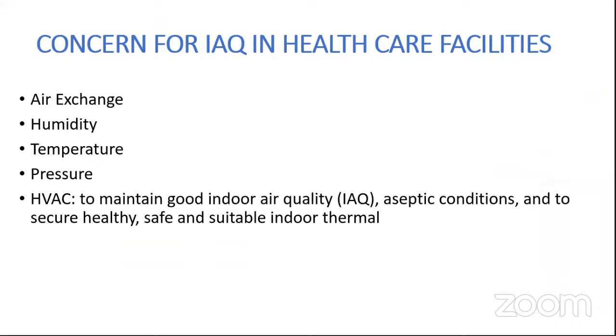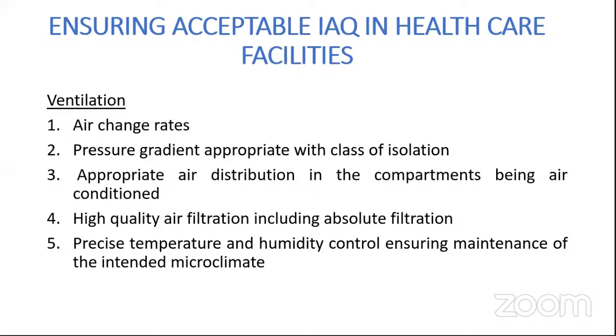Now, a concern for indoor air quality in healthcare facilities, I have jotted it down to the crux in terms of COVID. If we are talking about COVID, it is about air exchange. It is about the humidity levels, temperature, differential pressure, and the HVAC system which is working. So when we talk about ventilation, CO2 is regarded as one of the major surrogate indices for ventilation.